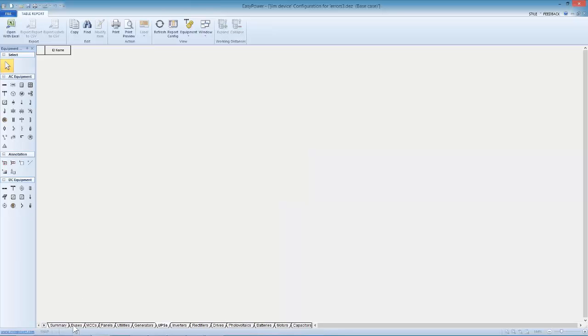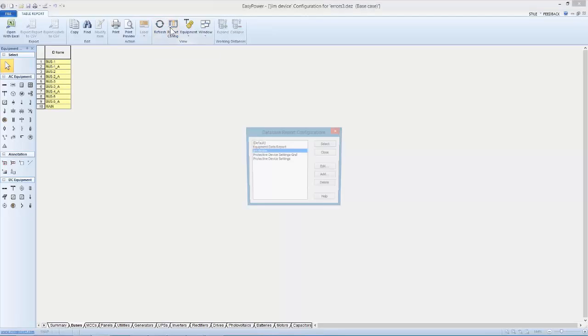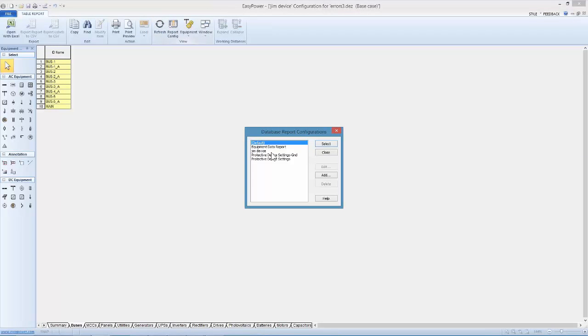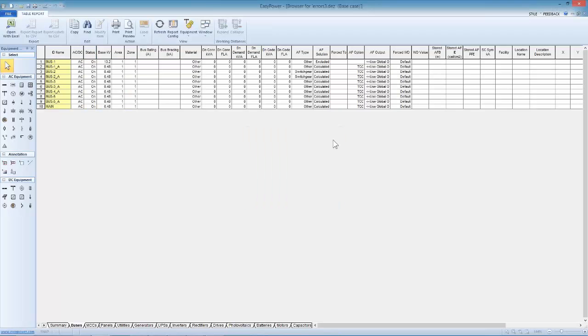One of the things that we kind of overlook and don't emphasize that much is that one of the criteria, or one of the things we're trying to determine as we're doing a study, is not only what the arc flash incident energy is, but whether the equipment at every point in our system can withstand the worst case fault, the worst case surge that it may ever see. And that is referred to as equipment duty.